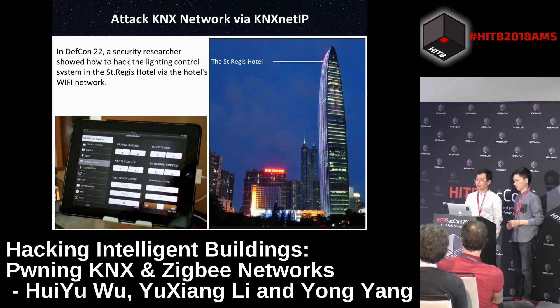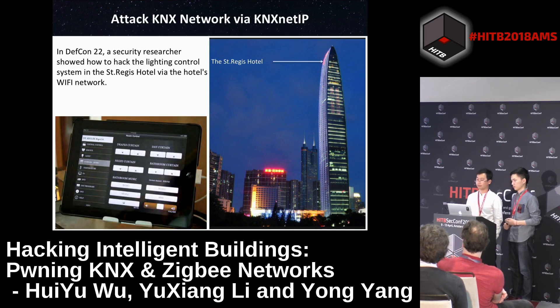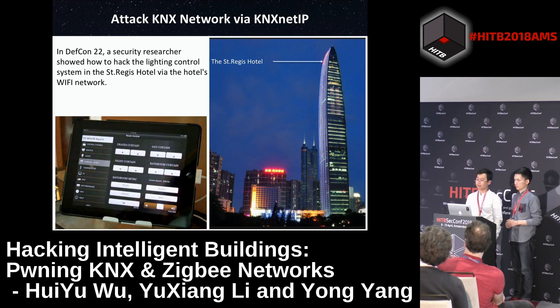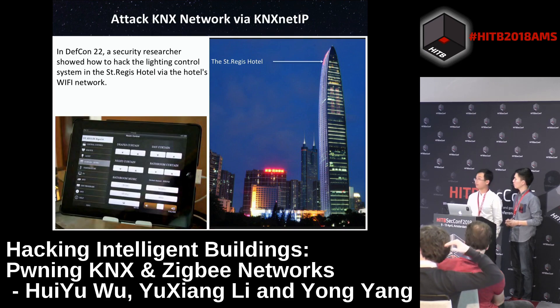In reality, a security researcher showed how to hack the lighting control system in hotels via the hotel's Wi-Fi network, and presented his research at DefCon 22. Because the KNX network was not isolated, after connecting to Wi-Fi, he sniffed the traffic and scanned the topologies of the entire network, and finally achieved the attack.